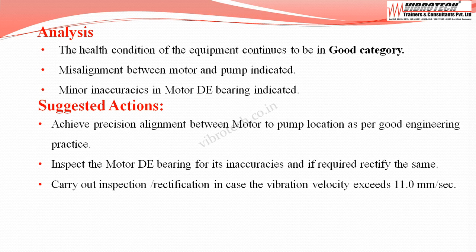As per the analysis, the suggested actions are as follows: achieve precision alignment between motor and pump as per good engineering practice; inspect the motor drive end bearing for inaccuracies and if required rectify the same; and carry out inspection and rectification in case the vibration velocity exceeds 11.0 mm per second.